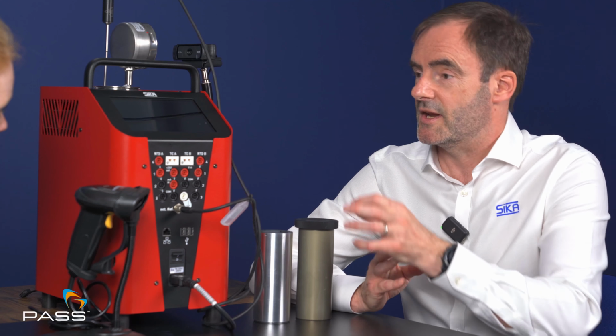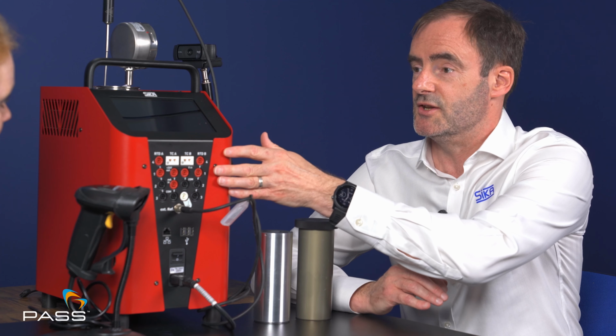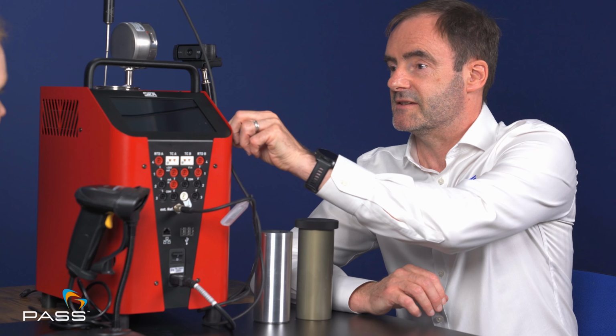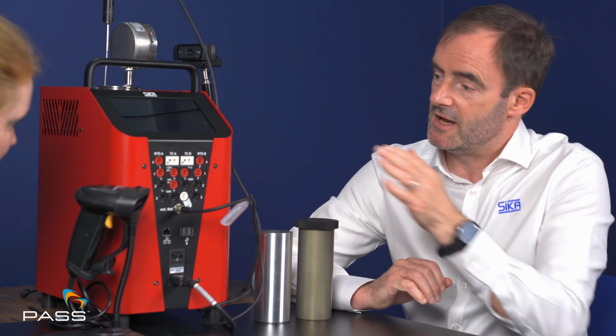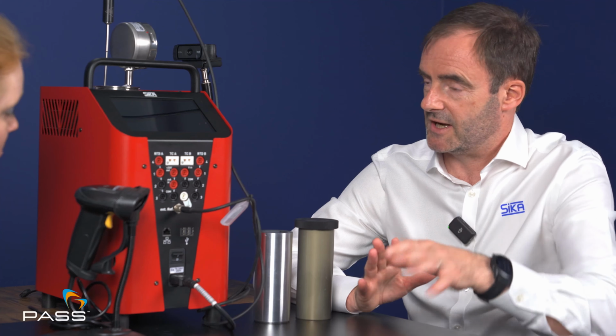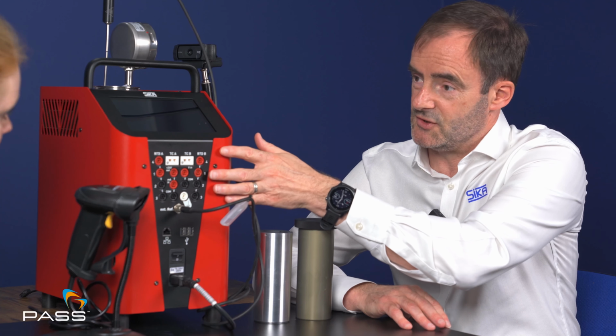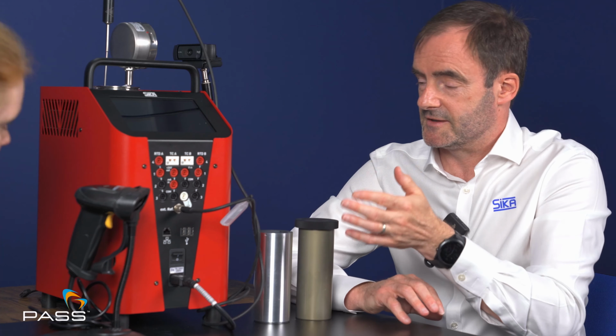One of the most laborious and time-consuming parts of any calibration job is the reporting. So how has Sika designed their premium multifunction temperature calibrators to improve this? When you calibrate a couple of units within the device, you can actually plug in your device under test into the Sika unit itself. And that will then take the measurements from the reference sensor and the device under test, and it'll populate the calibration sheet as they move through the different temperature thresholds that it's targeting. So it sort of does the reporting at the same time as doing the calibration? Effectively, yes. Most calibrators will expect the end user to write down the temperatures and then input that into a computer for an Excel spreadsheet or something, whereas with Sika, when we plug it into the instrument itself, that will actually generate that data for you. And as I say, it can be pulled out either as a PDF or in Excel format, and that's already done for you.